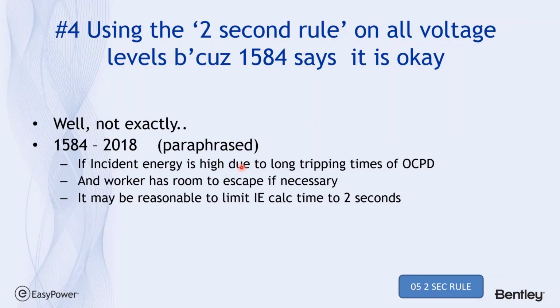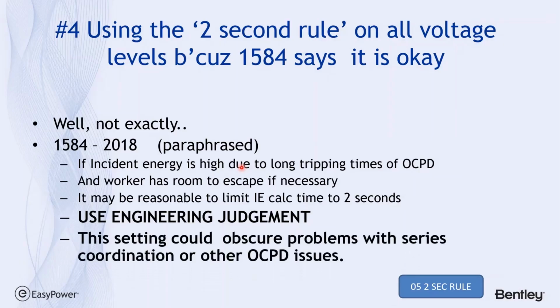It turns out if the incident energy is high due to long tripping times of the overcurrent protection device and the worker has room to escape if necessary, it may be reasonable to limit the incident energy calculation time to 2 seconds. But, and it's not even in fine print, they emphasize using engineering judgment. And I say that because putting a 2-second limit on the calculations prematurely at the very least could obscure problems with series or selective coordination.